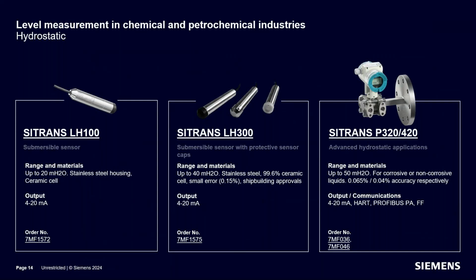The problem with using that type of measurement is the density of the product might change as the temperature changes and expands and contracts, the pressure changes, and that can all lead to error with regards to your levels. So this is a classic case where we're using a inferred measurement, in this case pressure, to try and tell us what the level is. But for whatever reason, if the application data sheet tells us that this is the best method for measuring your level, then that's the method we will go with.